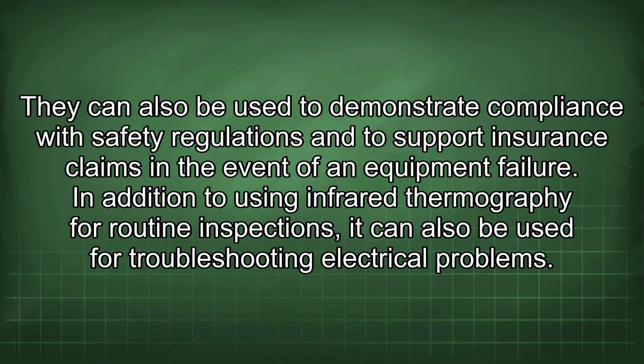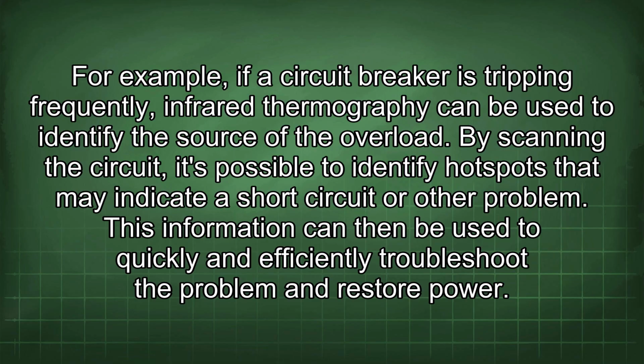In addition to using infrared thermography for routine inspections, it can also be used for troubleshooting electrical problems. For example, if a circuit breaker is tripping frequently, infrared thermography can be used to identify the source of the overload. By scanning the circuit, it's possible to identify hotspots that may indicate a short circuit or other problem. This information can then be used to quickly and efficiently troubleshoot the problem and restore power.